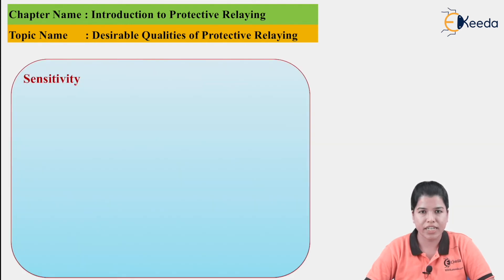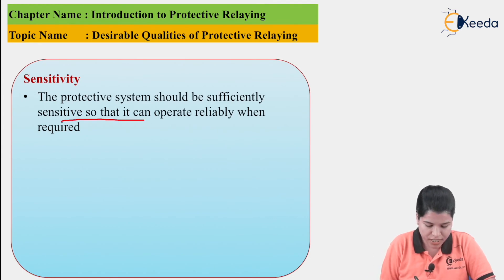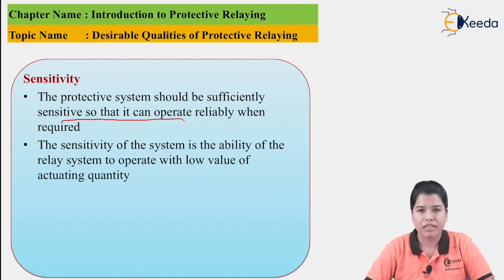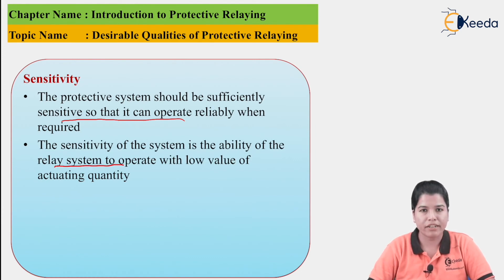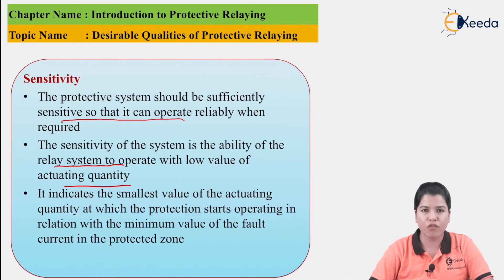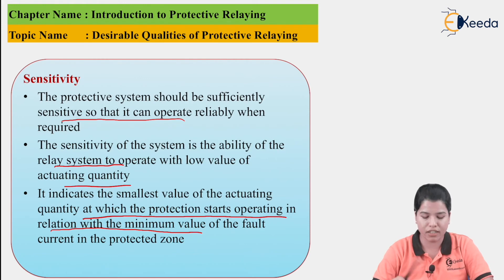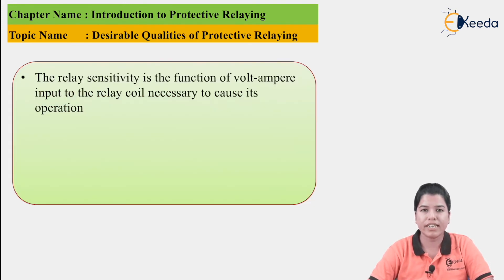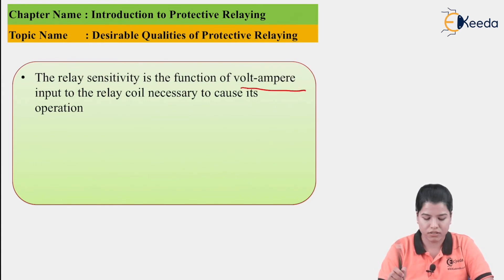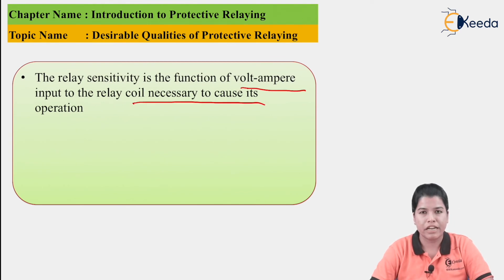The next desirable quality is Sensitivity. The protective system should be sufficiently sensitive so that it can operate reliably when required. Sensitivity is defined as the ability of the relay system to operate with a low value of actuating quantity — the relay must operate even for lower values of the actuating quantity. It indicates the smallest value of the actuating quantity at which the protective system starts operating in relation to the minimum fault current in the protected zone. Relay sensitivity is a function of the volt-ampere input to the relay necessary to cause its operation.